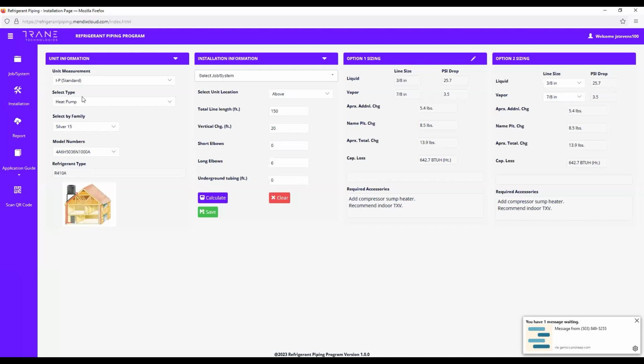Even though it's okay to use it on some line sets, not for this. So let's try 3/4. Pressure drop is high, but it's yellow. So this means if you absolutely had to, you could use this, but you don't want to. You want to go ahead and use 7/8. Anything that is white is good. You know you can do it, no problems. Yellow is caution. Red is do not do. Is that better?